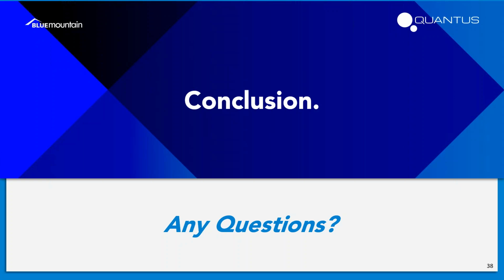Excellent. Next question. Could you comment at a high level on the definition of a loop and a system feature? And I think that's specific to BMRAM is my guess. So I'll field that. From a loop perspective, the intent of the loop is an instrument loop. So you have your sensor, your transmitter, and a display potentially, or a chart recorder, right, that you would have as loop members, and you calibrate that as a loop. Typically, you're calibrating that entire loop when you do a calibration.